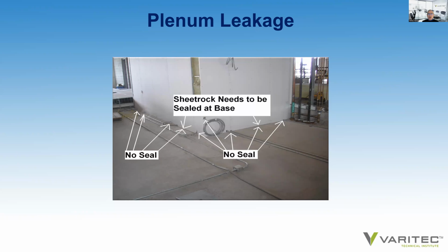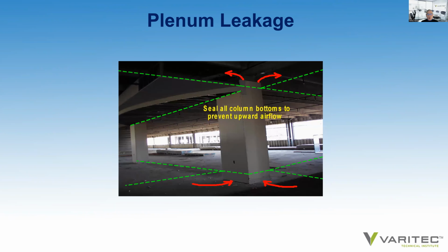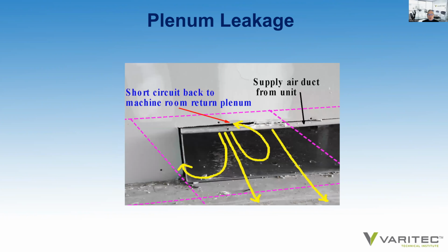So you want to look at wherever drywall comes into direct contact with the floor and make sure that that drywall is properly sealed. It's amazing how small orifices can result in leakages cumulatively throughout the floor plenum. You want to look at columns and where drywall comes to the floor. You want to look at making sure that any duct entry points are properly caulked and sealed.